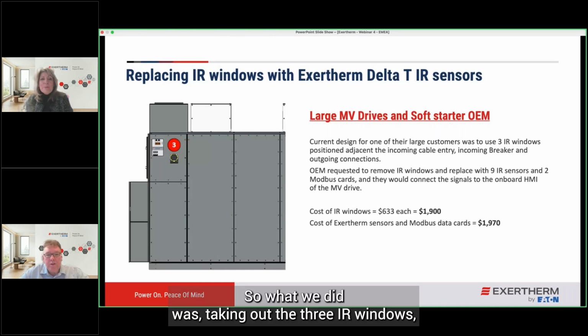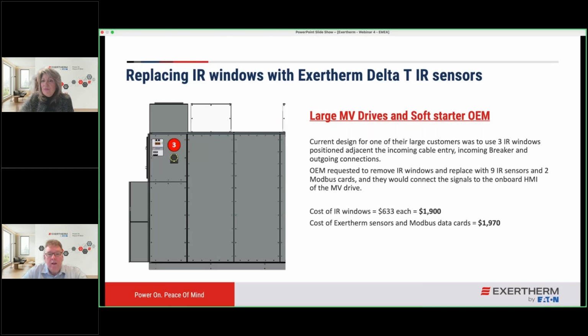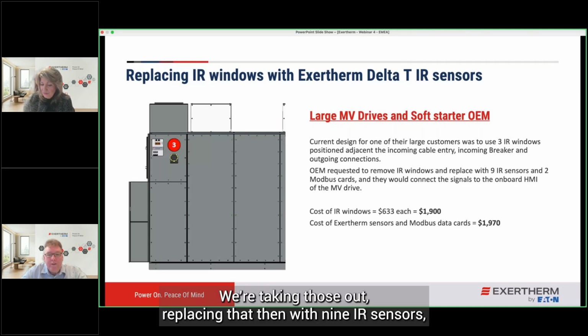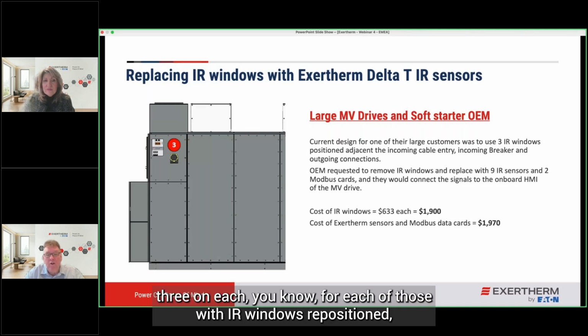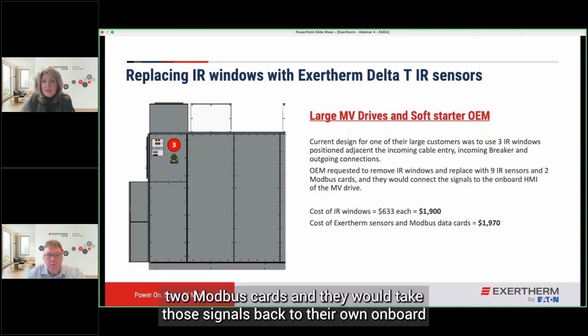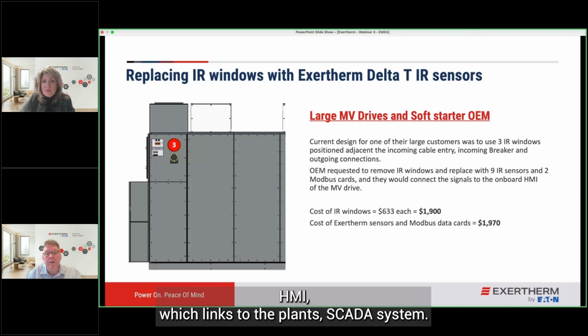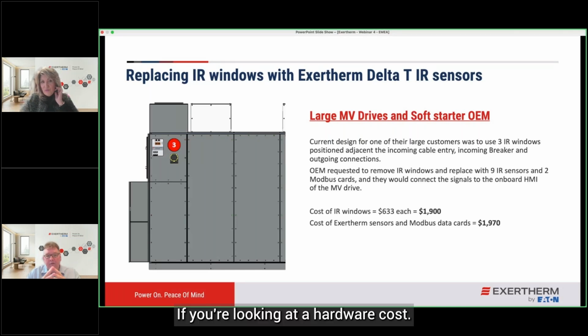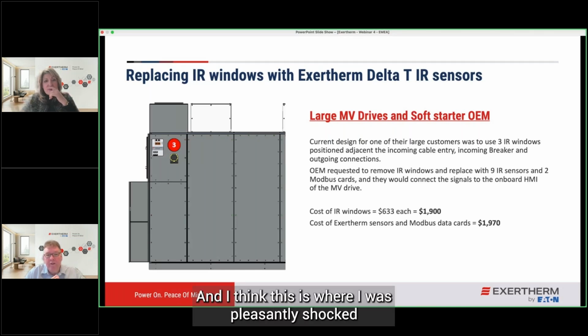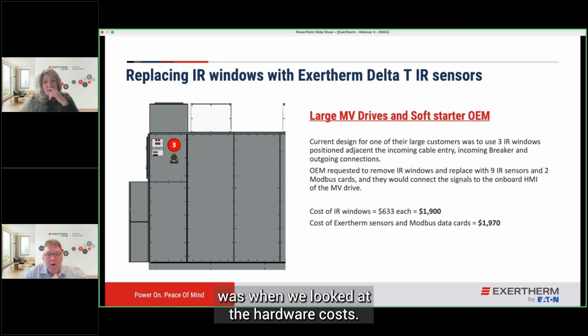So what we did was take out the 3 IR windows, which were from a renowned brand, and replace them with 9 sensors, 3 on each of those where the IR windows were positioned, and 2 Modbus cards. They would take those signals back to their own onboard HMI, which links to the plant's SCADA system. If you're looking at hardware cost, and I think this is where I was pleasantly shocked, when we looked at the hardware costs.